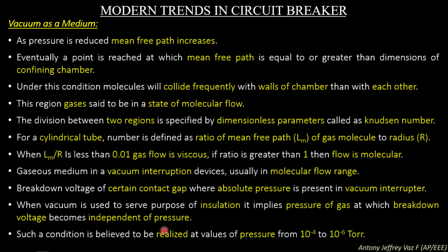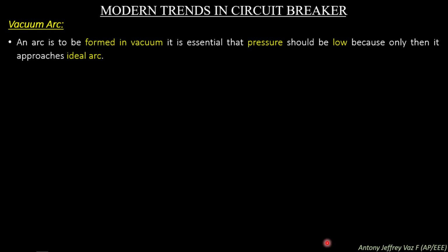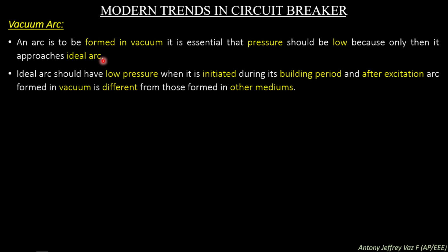So a complete vacuum provides a very high insulation between the contacts of the circuit breaker. Such a condition is believed to be realized at values of pressure from 10 power minus 4 to 10 power minus 6 torr. So this high vacuum, or low pressure, is realized at 10 power minus 4 to 10 power minus 6 torr. If an arc is to be formed in vacuum, it is essential that the pressure should be low, because only then does it approach the ideal arc. So the characteristics of the arc will be the same as the ideal characteristics of an arc in air.